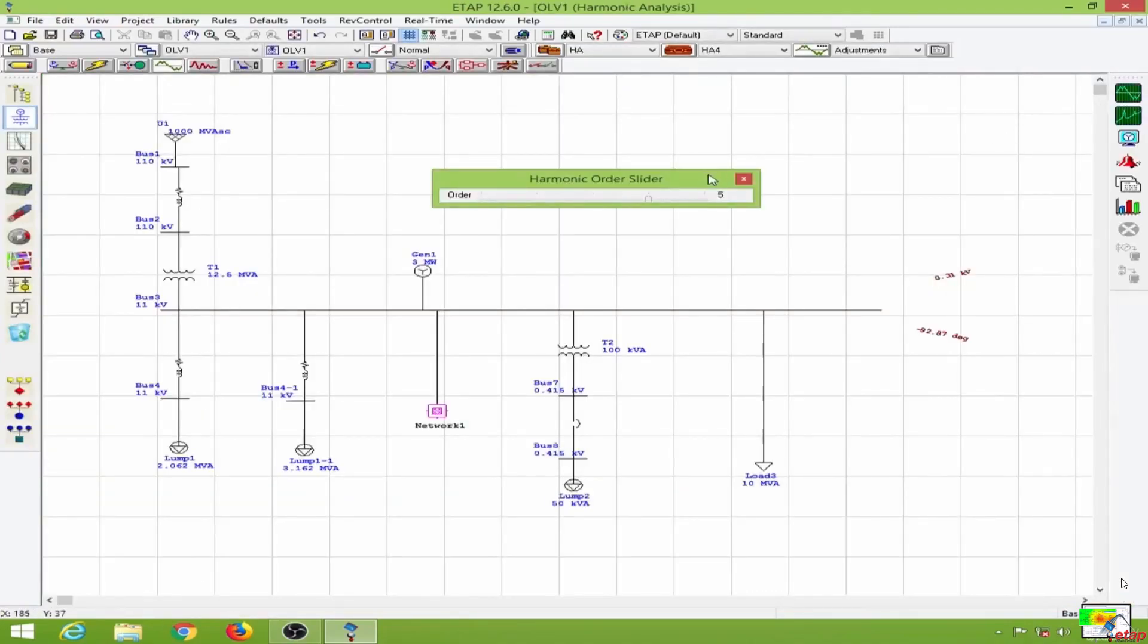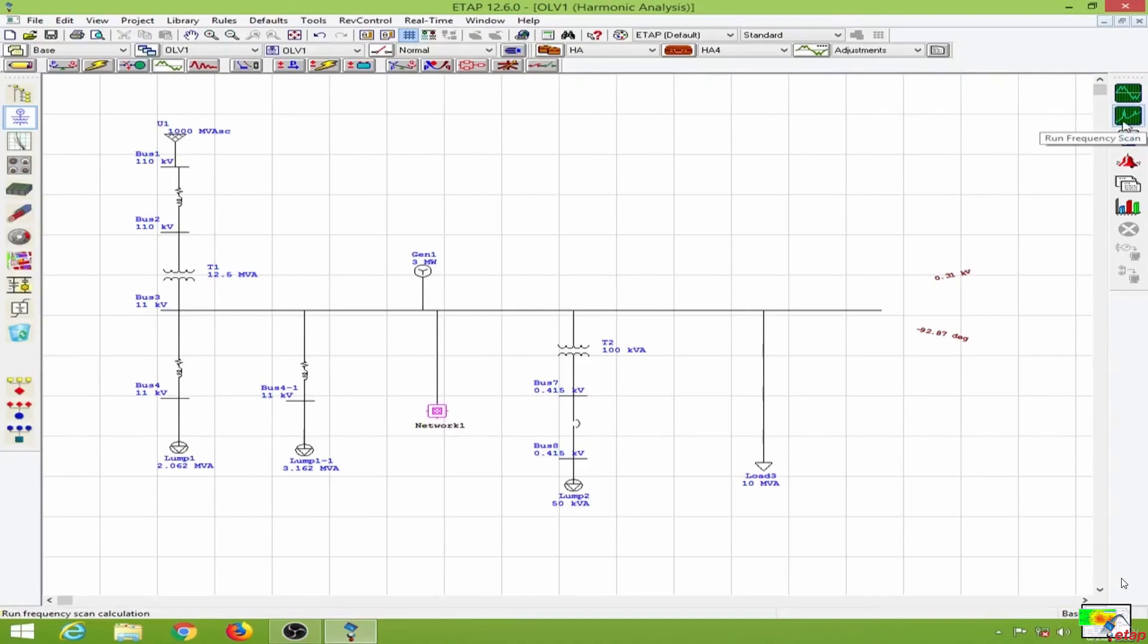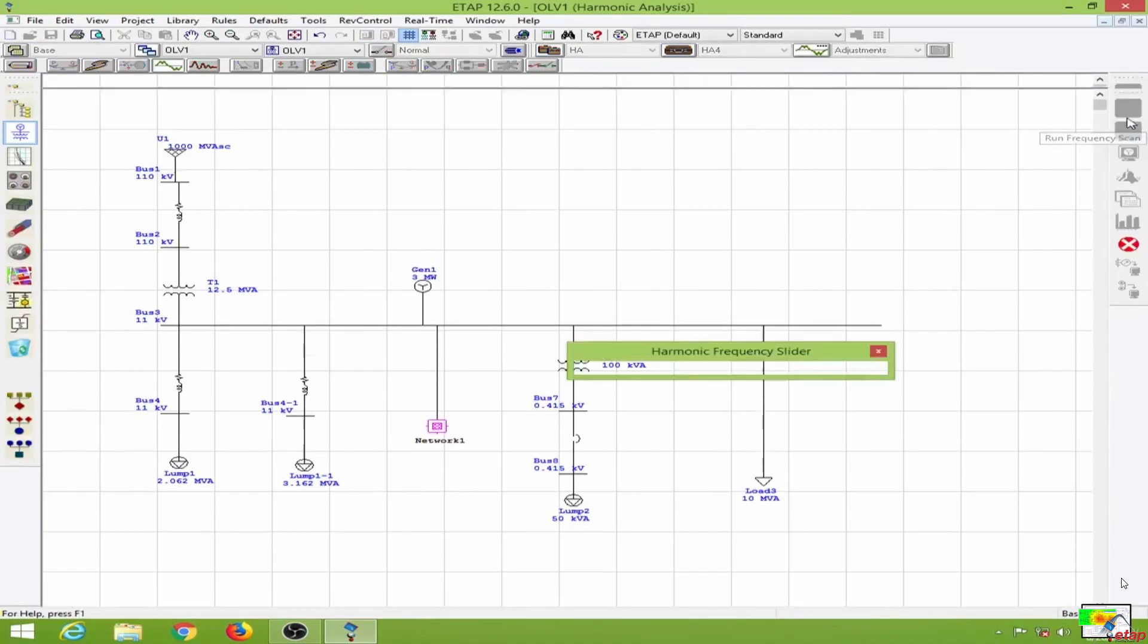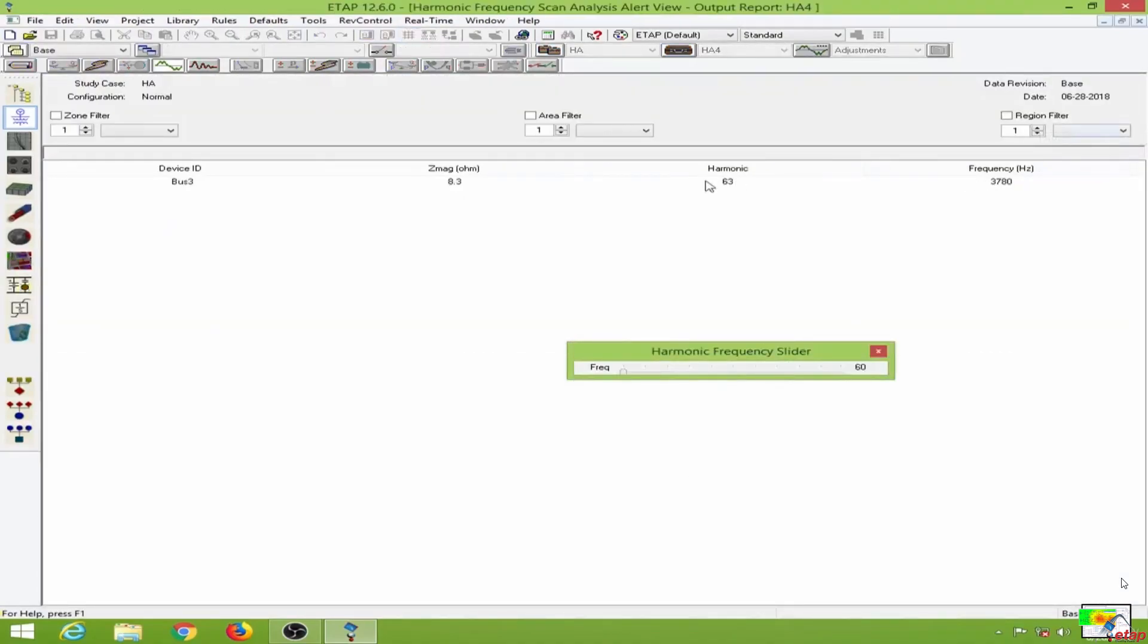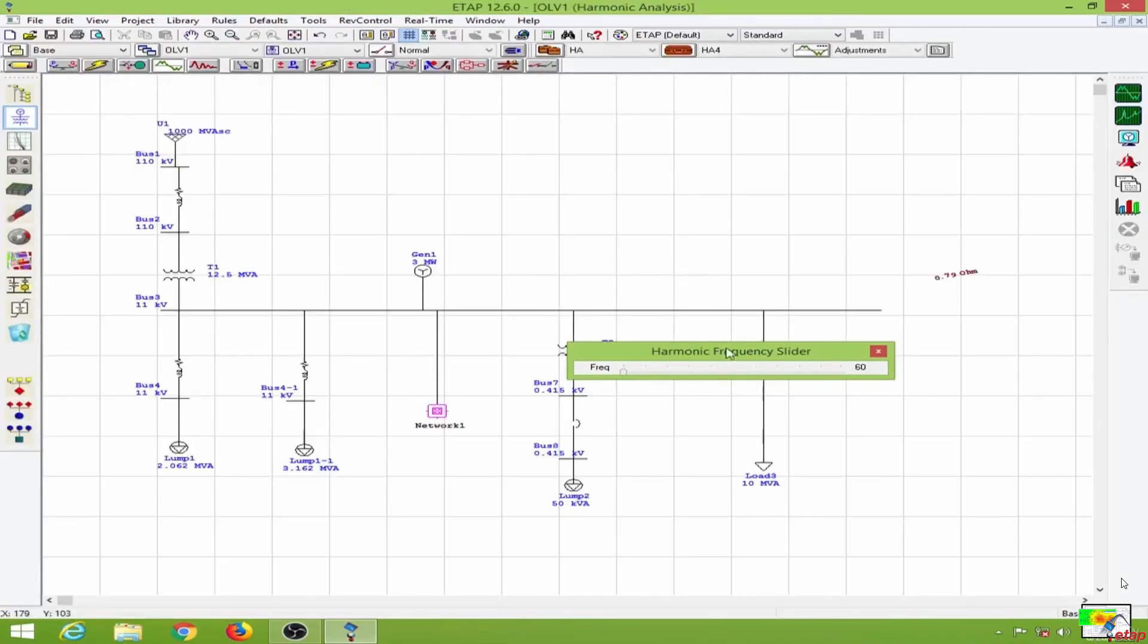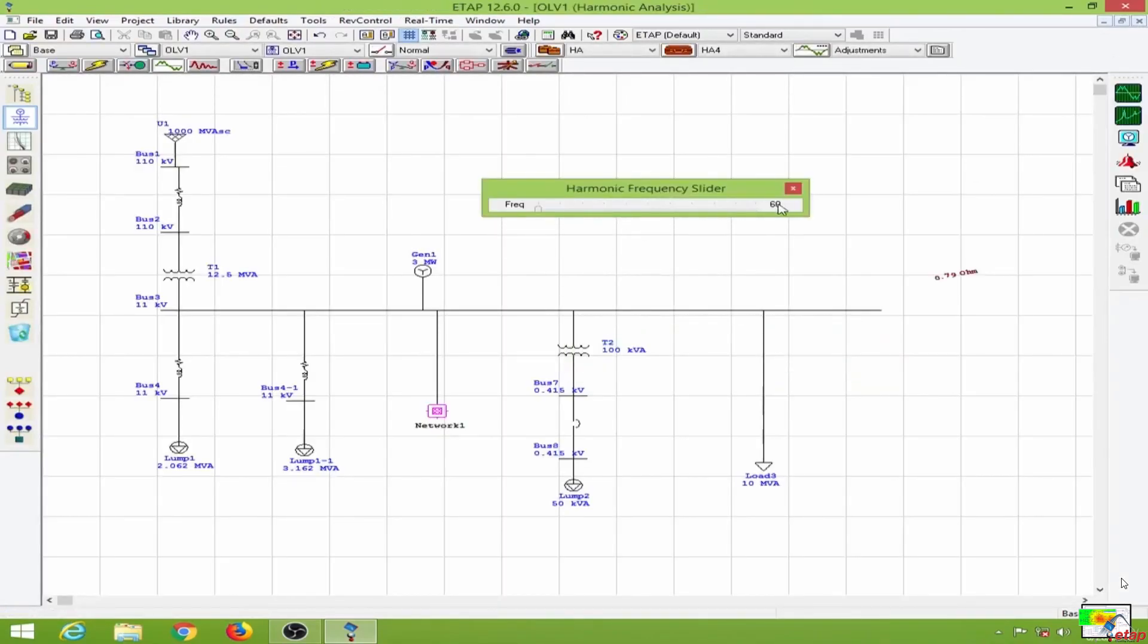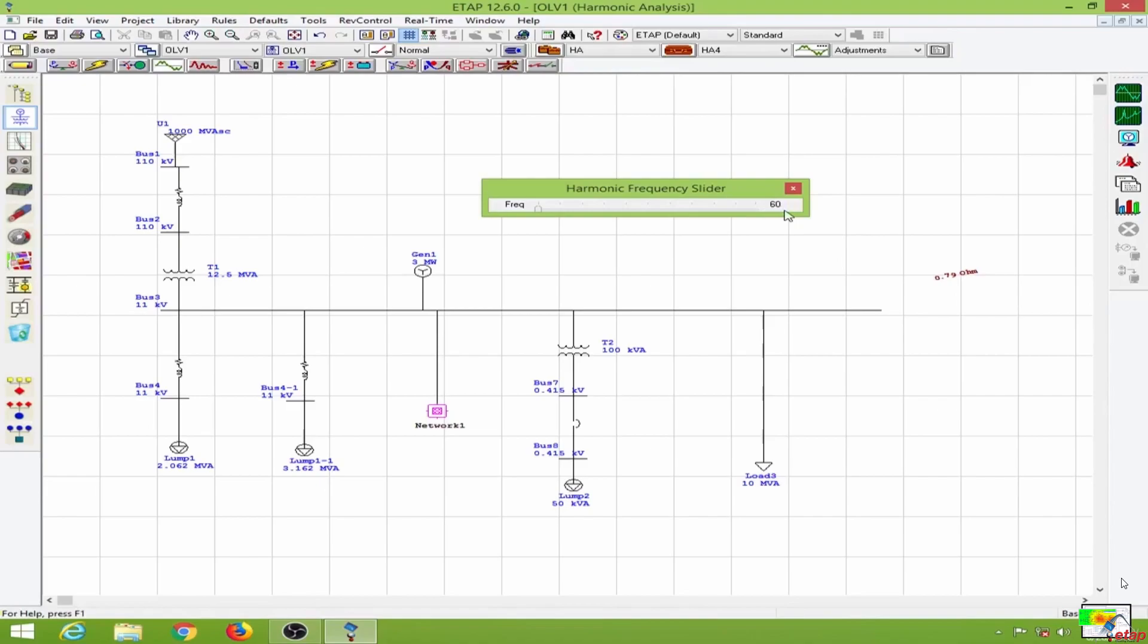Next, I want to show you the frequency scan. Running the frequency scan, we go to the alert window. Let me close this. This system is operating at 60 hertz fundamental frequency. At 60 hertz, we have about 0.79 ohm impedance towards this frequency. If I change the frequency, you can see the impedance value changes accordingly.